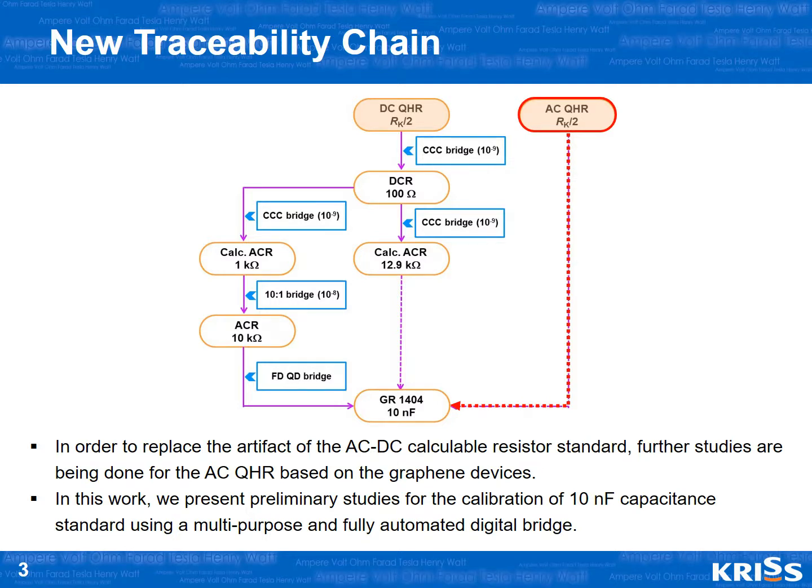In this work, for the ultimate goal of tracing the capacitance from the AC quantum Hall resistance, a preliminary study has been done for evaluation and calibration of a 10 nanofarad capacitance standard using a multi-purpose and fully automated digital bridge.